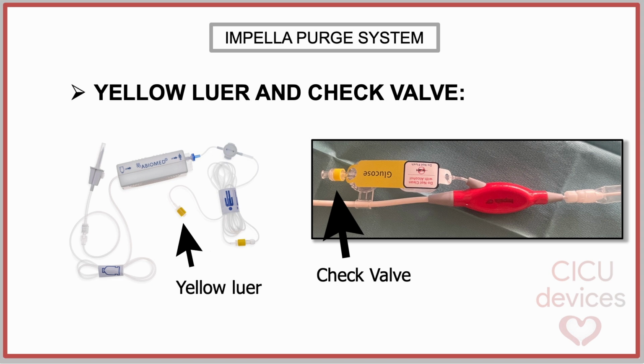The tubing terminates in a yellow luer connector or yellow luer lock, which interfaces with the corresponding yellow luer on the Impella catheter. This last component is referred to as the yellow check valve, as it incorporates a valve mechanism that enforces unidirectional flow of the purge solution from the console toward the catheter, thereby preventing any retrograde flow of purge fluid during disconnections.